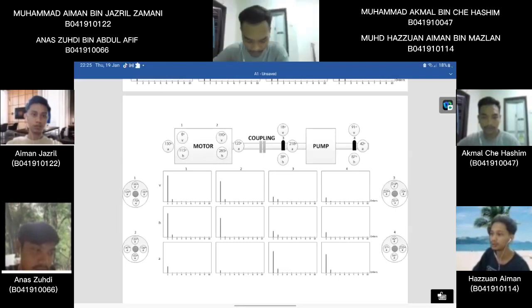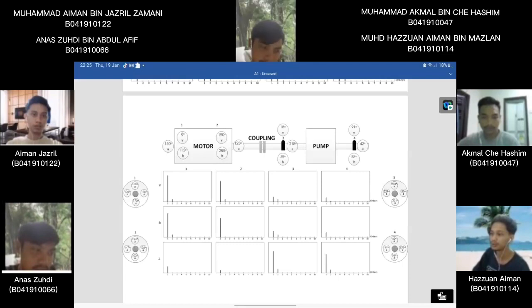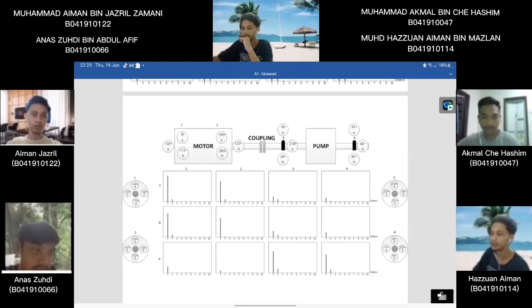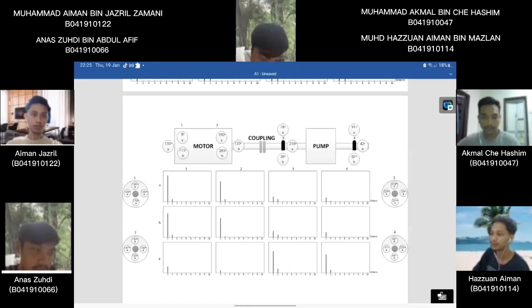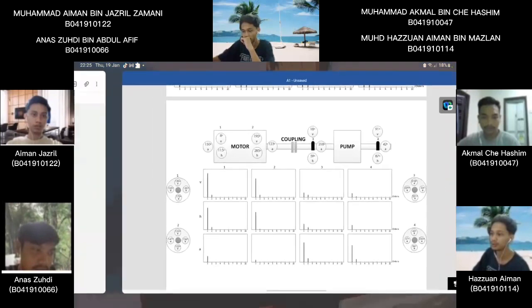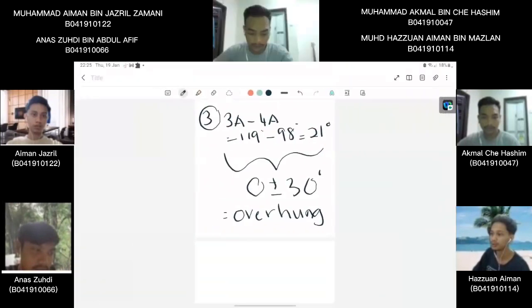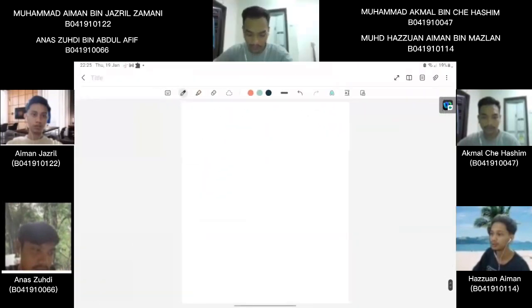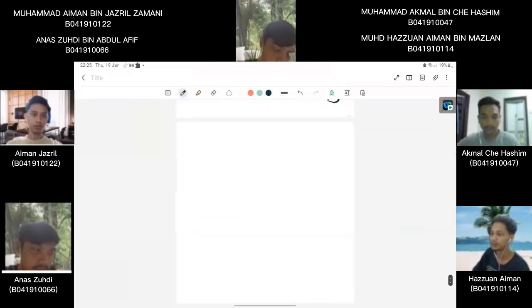Radial is bigger than axial, right? Yes, it's obvious. And criterion number 2: is 1x dominant? True. There are two line spectrum terms, 1x and 2x, and the dominant is 1x. For the motor, okay.